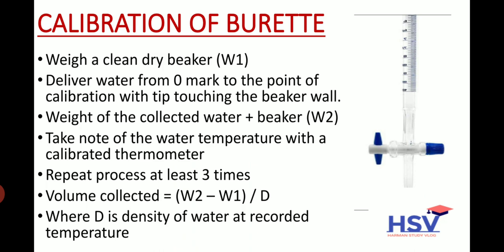To calibrate a burette: weigh a clean dry beaker (Weight 1), then deliver water from the zero mark to the point of calibration with the tip touching the beaker wall. The weight of the collected water plus beaker is Weight 2. Note the water temperature with a calibrated thermometer. Repeat the process at least three times. Volume collected = (Weight 2 − Weight 1) / d, where d is the density of water at the recorded temperature.